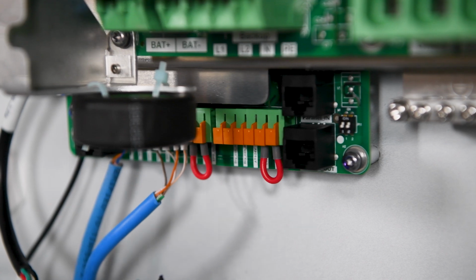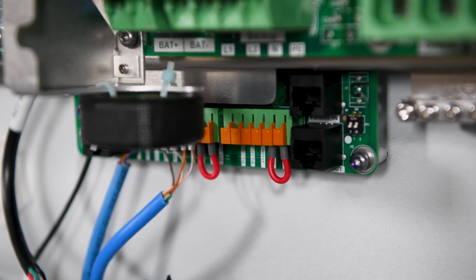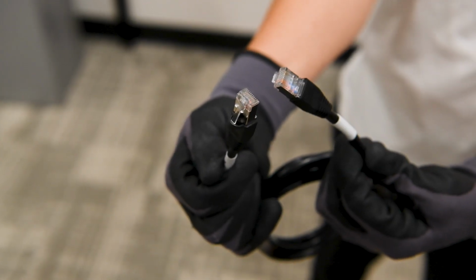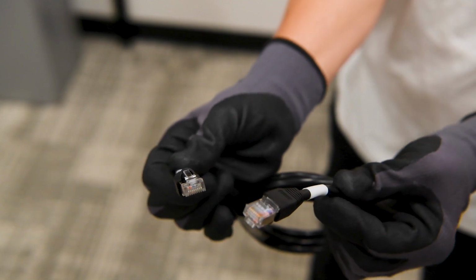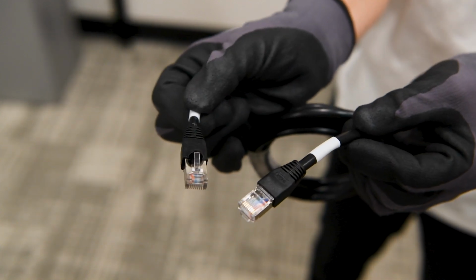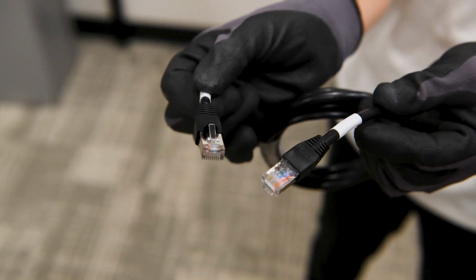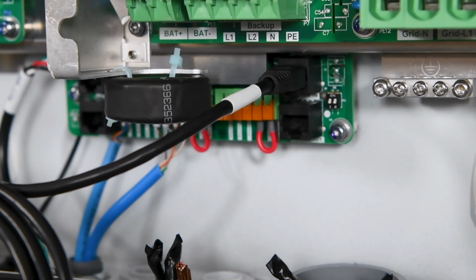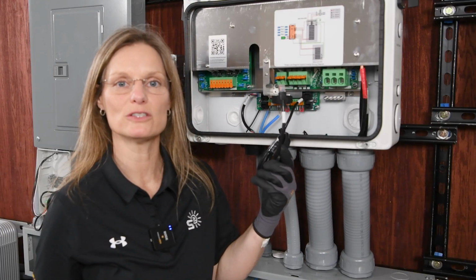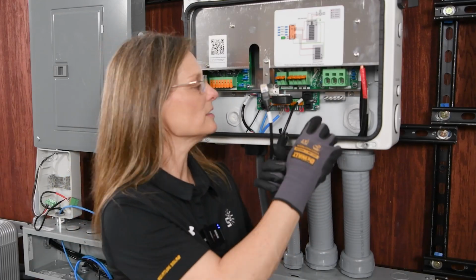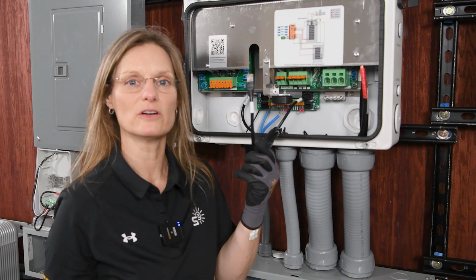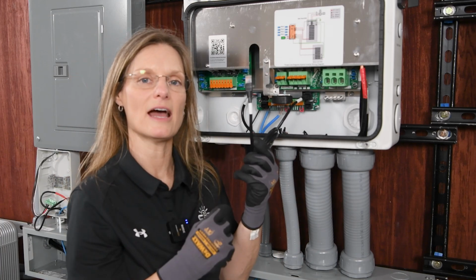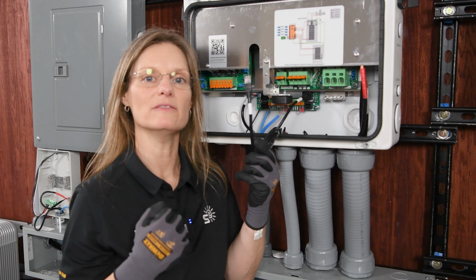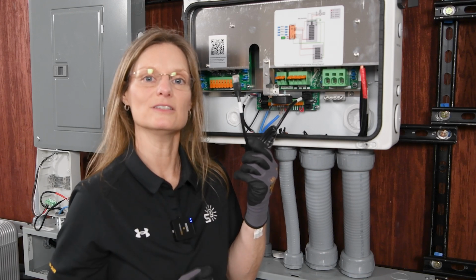The last thing you'll see on your communications board are your paralleling ports. Inside your accessories kit, inside your inverter box, you will find the paralleling cable. You'll simply take your standard Ethernet cable and plug one end into your in port inside your master inverter, and the other end will go into the out port of your slave inverter, and you will continue to go in to out into each inverter that you have in your system up until you get to 6.